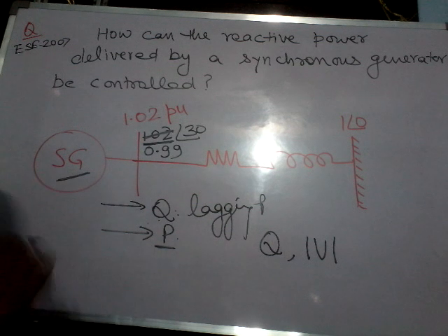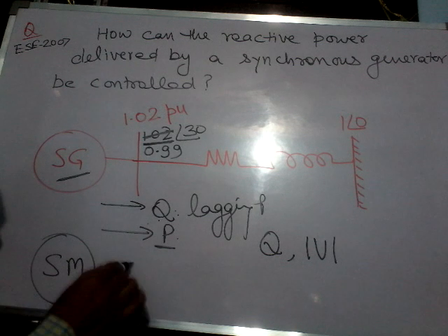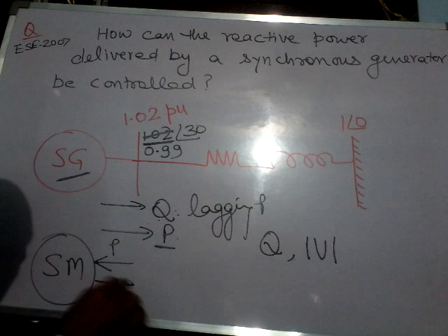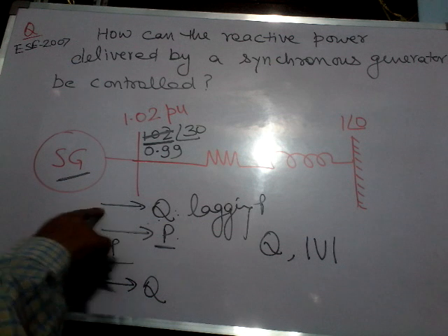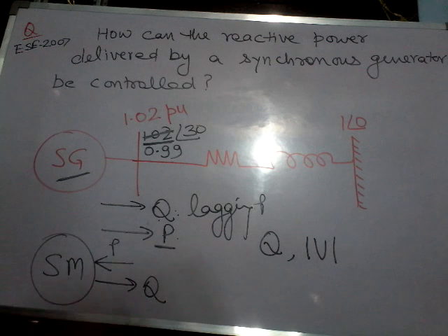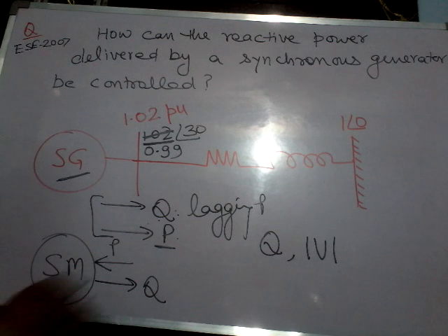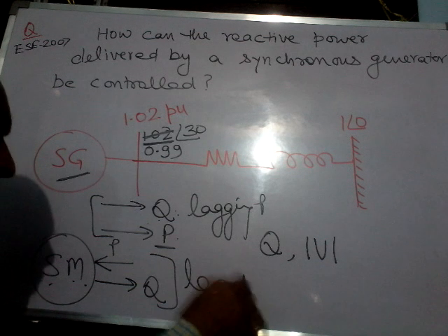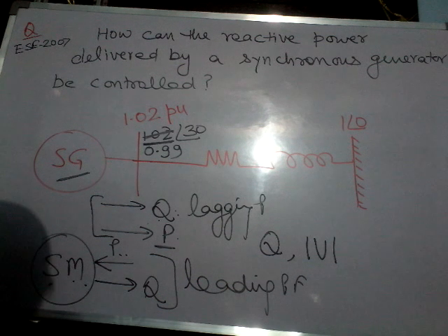If it is a synchronous motor, a motor will always consume P. But if the synchronous motor is running at high excitation, it will also supply reactive power. If a synchronous generator is running at high excitation, it will supply Q, and if a motor is running at high excitation, it will supply Q. No problem. But in the generator case it is lagging power factor, while in the case of the motor at high excitation it is leading power factor, because the direction of P and Q is opposite.